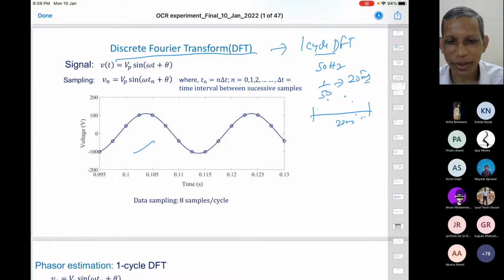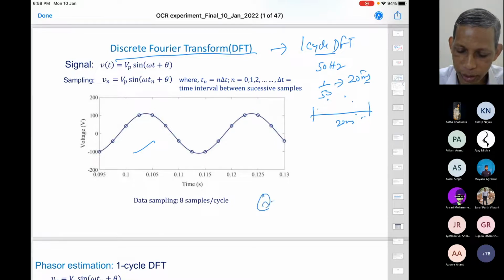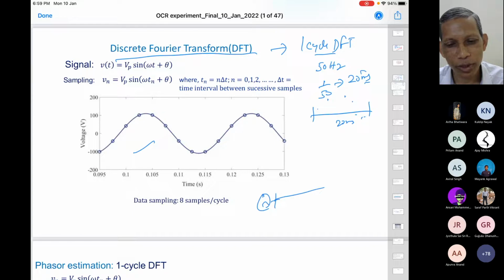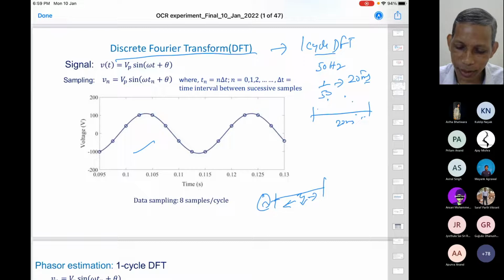Not a problem. What you are saying is correct. From the high frequency component also you can make a judgment. Kuldeep is working on this. Whenever a fault happens, we'll have a traveling wave, with a sudden change in voltage and current, which will propagate from this side to that side. That can also be used here. But mind that the purpose of the relay is to identify whether there is an internal fault or not. So you can use harmonics, you can use traveling waves, you can use the fundamental also.